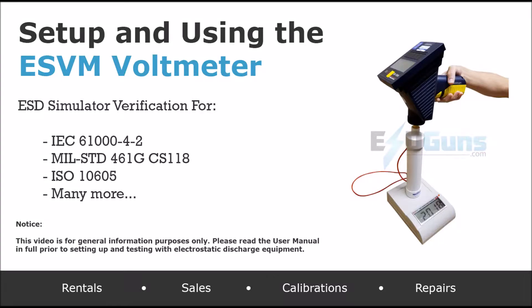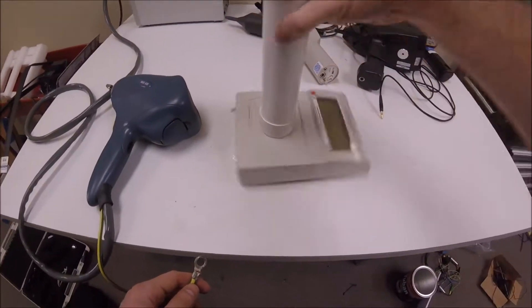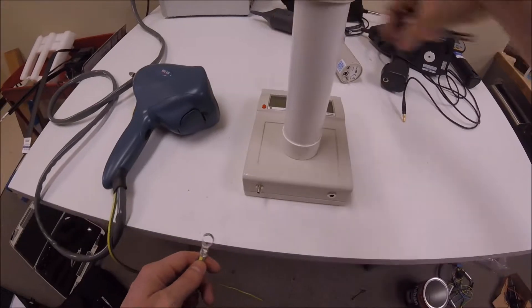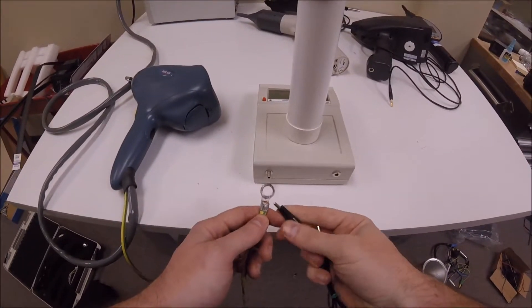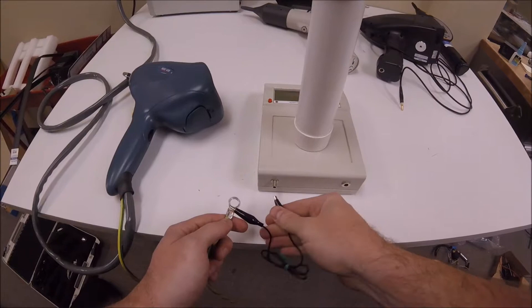The ESVM meter is a simple unit for verifying the output voltage of your ESD simulator. Starting with the NSG438, which has a closed loop on the ground cable, we can use an alligator clip to connect to the ground on the meter.